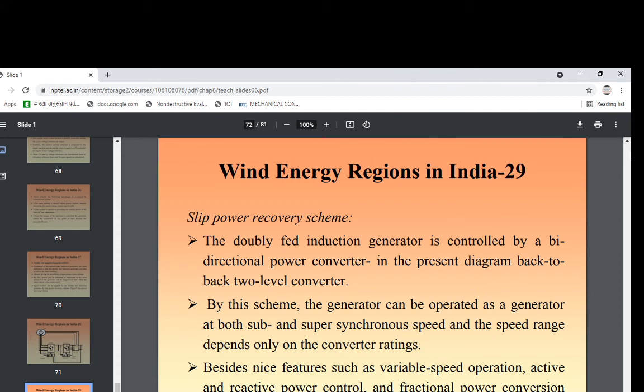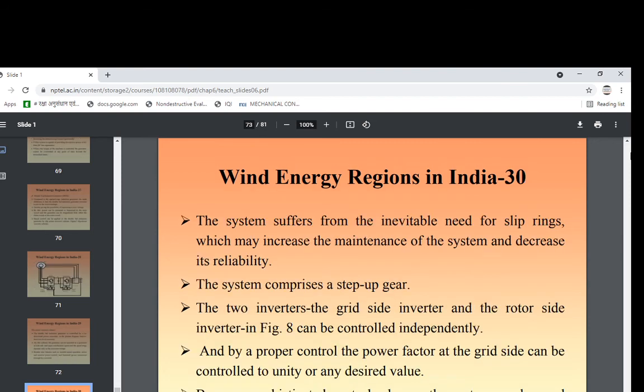By this scheme, the generator can be operated as a generator at both sub and super-synchronous speed, and the speed range depends only on the converter ratings. Besides nice features such as variable speed operation, active and reactive power control, and fractional power conversion, the system suffers from the inevitable need for slip rings, which may increase the maintenance of the system and decrease its reliability.